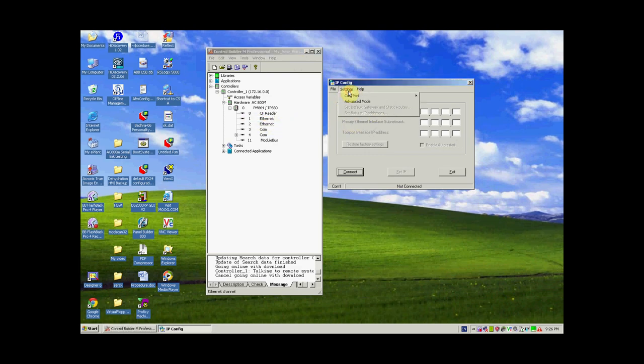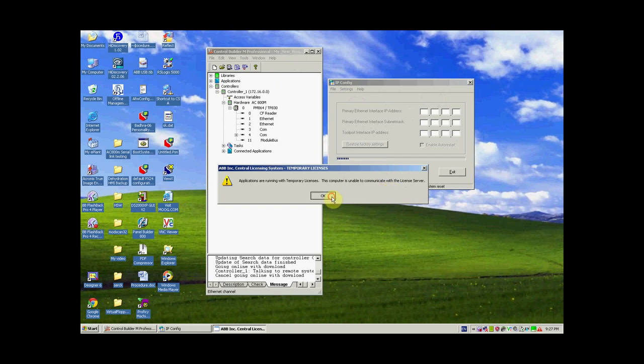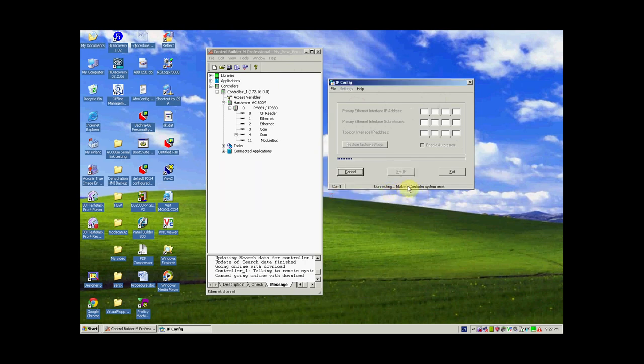Make sure COM1 is selected, as we have used the TK212 cable on COM1. Select COM1 if you have multiple COM ports. Click Connect. A message will appear: connecting to the controller — system reset. System reset means pressing the INIT button on the AC800M controller. Briefly press it until the Run LED blinks.